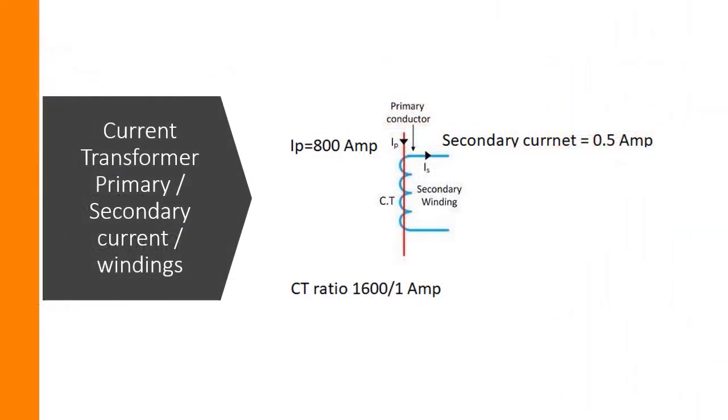Welcome back. In this section, we will see and study the current transformers' theory. You can see in this picture this is basically the current transformer symbol. Primary current is the current that goes through the conductor. Secondary current is from the secondary windings. In this example, this is a 1600 to 1 ampere CT. If the primary side has 1600 ampere current, there will be 1 ampere secondary current.